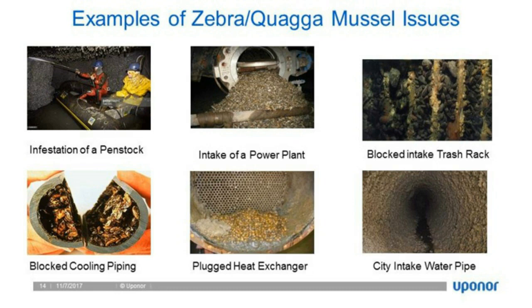The other aspect is that not only do you reduce the diameter of your pipe, but when we take a look at hydraulic fluid movement, the smoothness of the surface of a pipe also contributes to the hydraulic flow values of fluids. So the rougher the surface, the higher the energy needed, and the harder it is to pump through that pipe. So not only does it block, but it also increases operational costs because it's harder to pump water through the pipes.